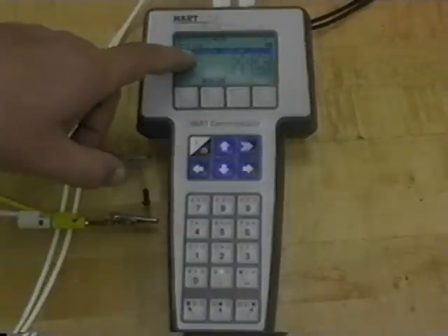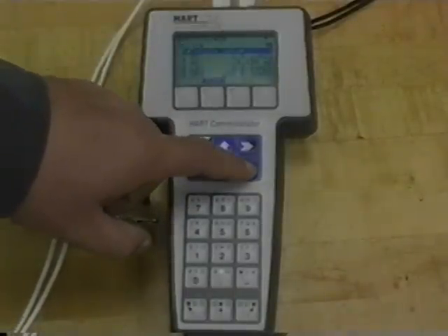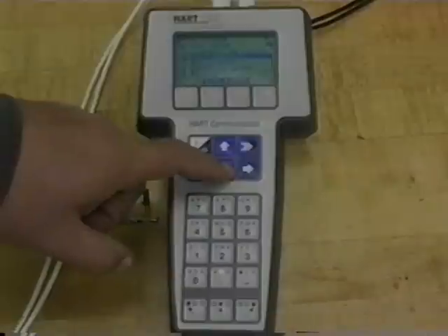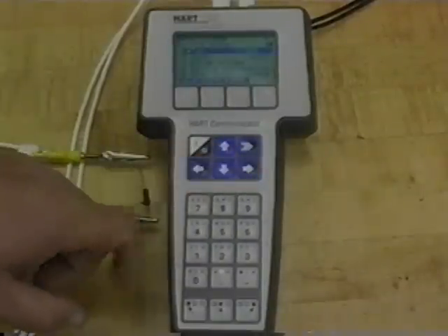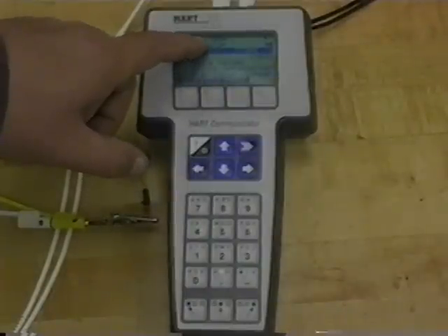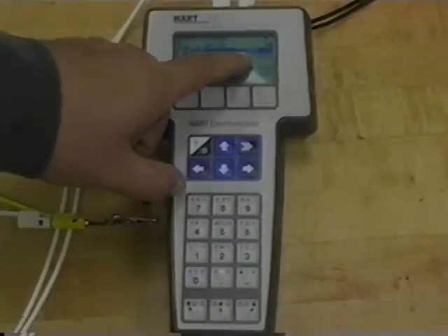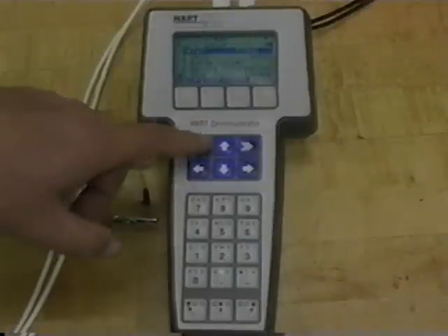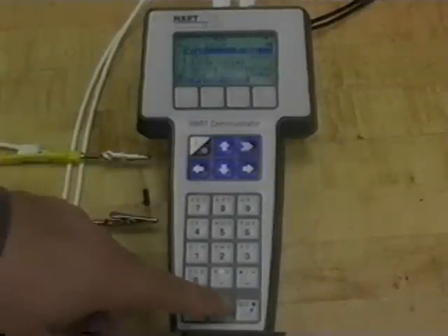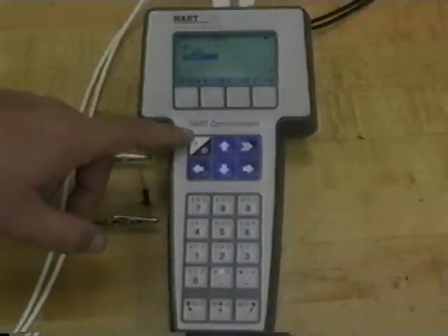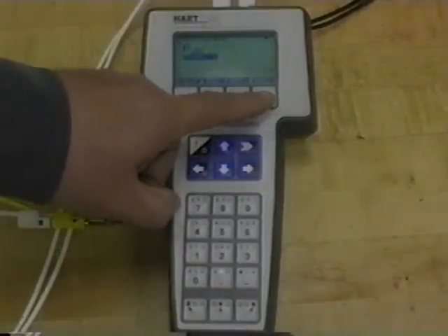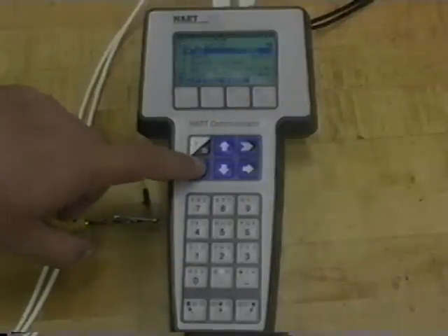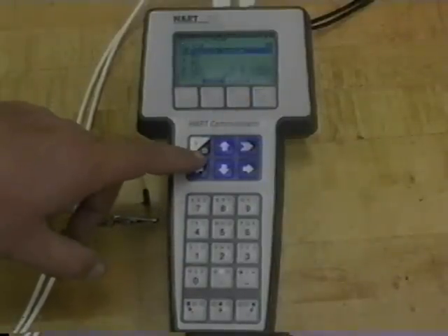If I stay on the device setup and move over to the right and come down to basic setup and move over to the right, you can see the tag LT430. I'm going to change it to PT101. PT101's already in there. I just need to set it to the transmitter.